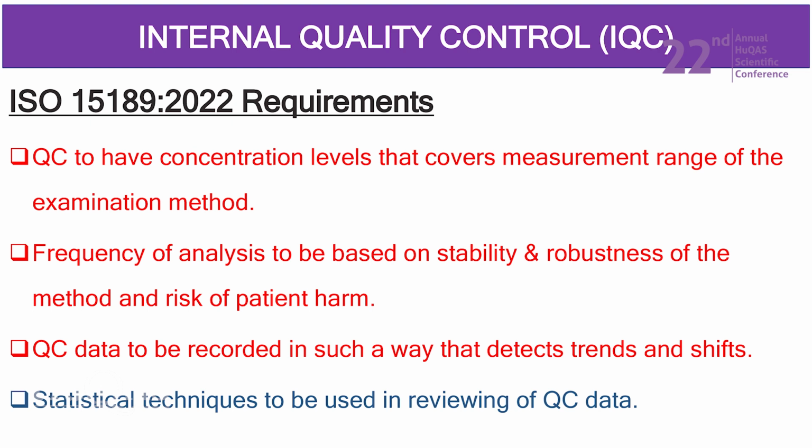So you're being advised that now the IQCs we put in place or that we engage for our machines should cover the entire measurement range of our analyzers. And therefore, the issue of buying just one level of IQC is highly prohibited now in this new version of the standard. That we need to take note.